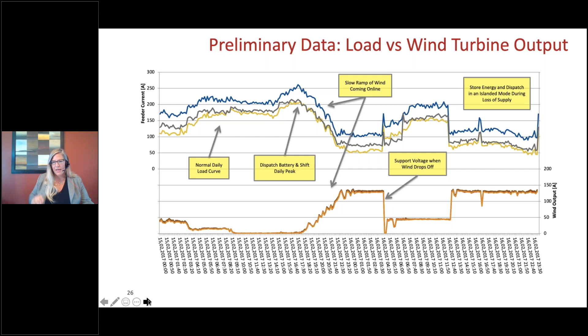Some preliminary data: the lines on top are the 3 phases of recloser data at the substation, and the bottom line is the output from the 6 megawatts of wind. You can see that when the wind is generating, there's a clear impact at the feeder head from pushing energy back. When something happens to the wind or the generator shuts off, there's potential impact on grid assets where taps change more than normal. So having a battery with the capability to ramp up and down in response to the wind generation signal is also an asset management benefit for us.